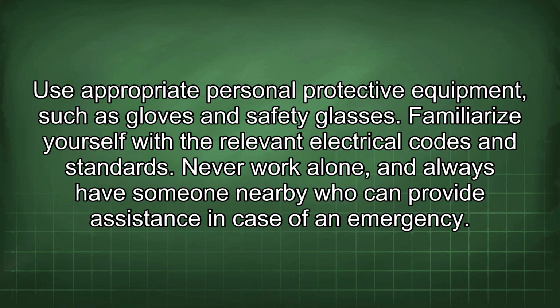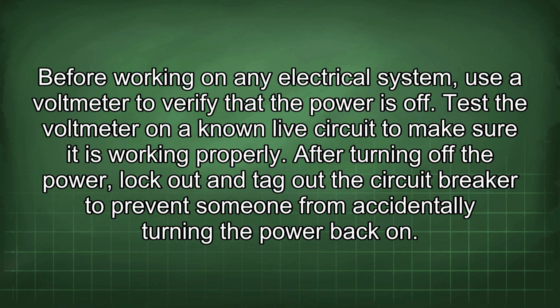Use appropriate personal protective equipment, such as gloves and safety glasses. Familiarize yourself with the relevant electrical codes and standards. Never work alone, and always have someone nearby who can provide assistance in case of an emergency. Before working on any electrical system, use a voltmeter to verify that the power is off. Test the voltmeter on a known live circuit to make sure it is working properly. After turning off the power, lock out and tag out the circuit breaker to prevent someone from accidentally turning the power back on.